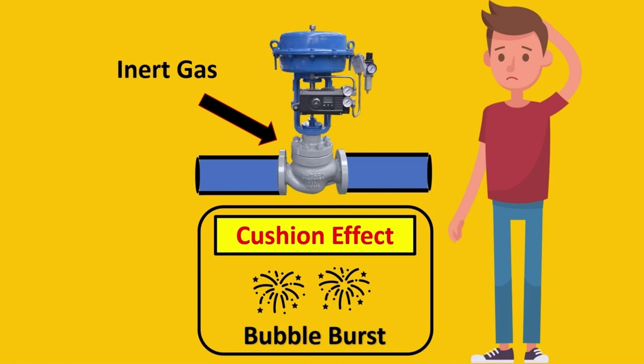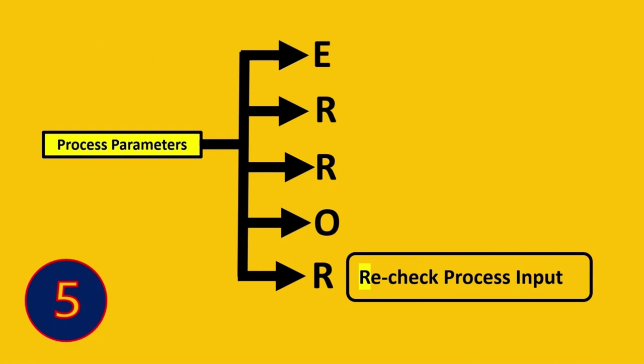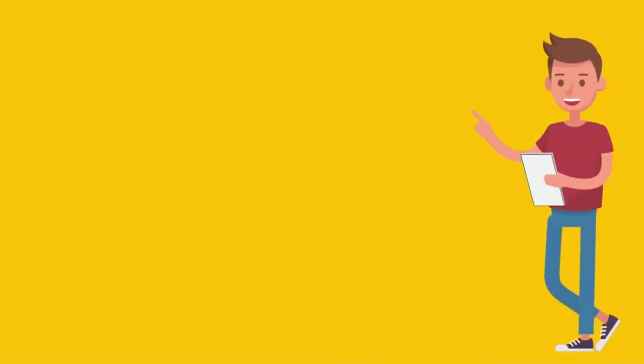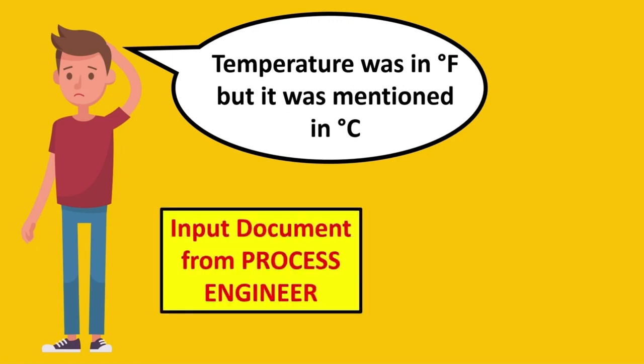The final one is my most personal example, which is R - recheck the process input. What happened with me was I was working on all the calculations and couldn't find a proper solution to cavitation. I went to the process department to ask and realized the temperature had to be in degrees Fahrenheit, but by mistake it was mentioned in degrees Celsius. If you're not able to find solutions to cavitation, just check if the input document from process is correct - all the process parameters, pressure drop, temperature, etc. Maybe that could solve your problem.